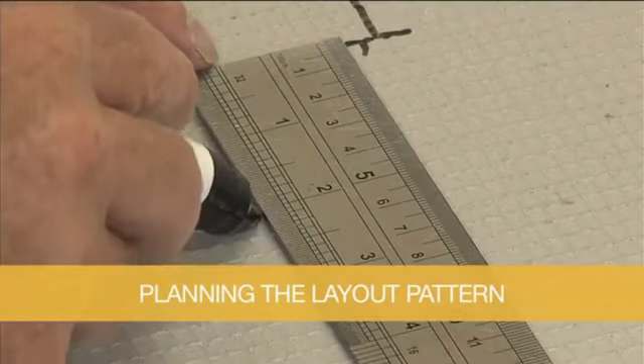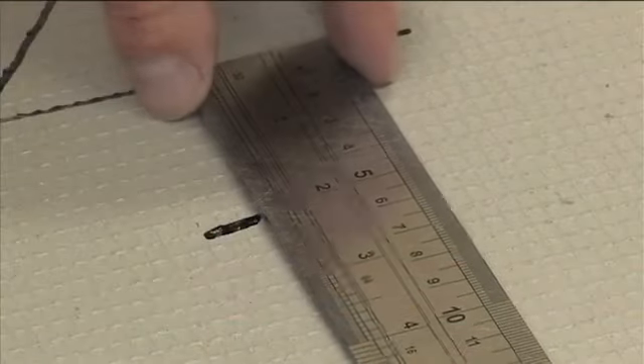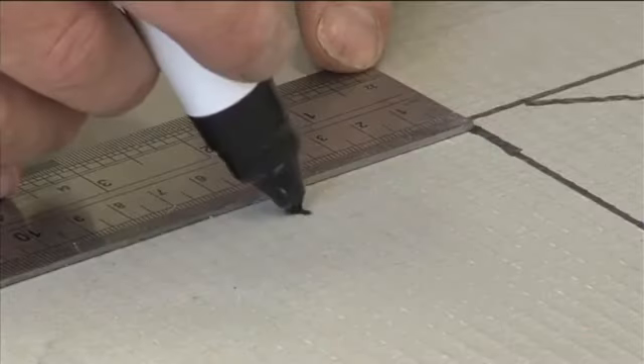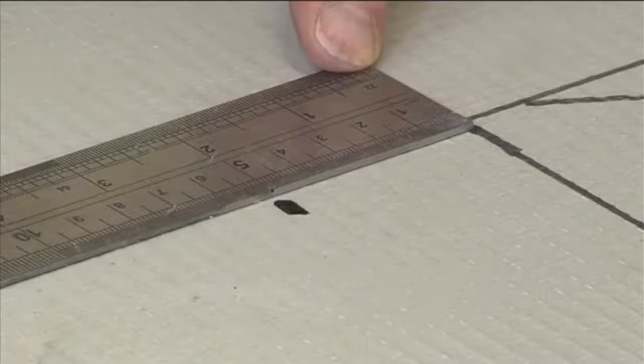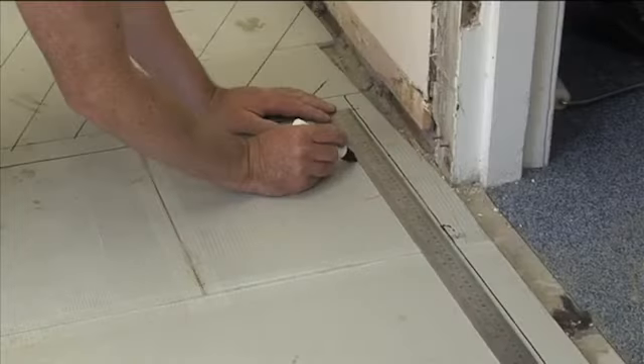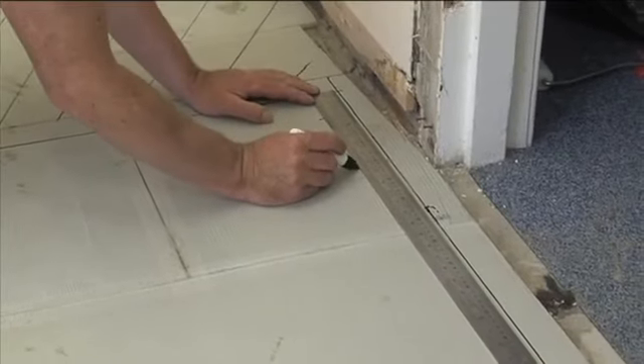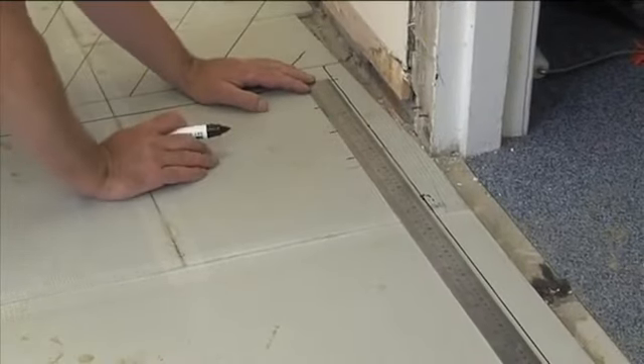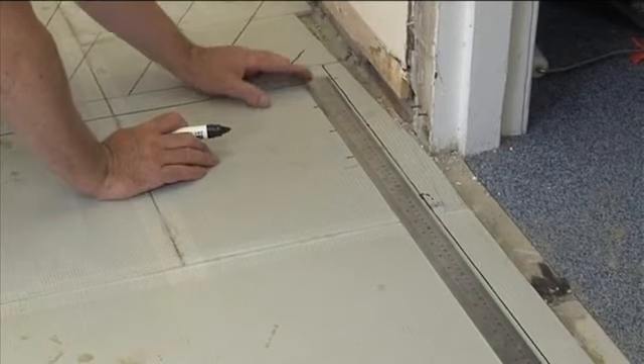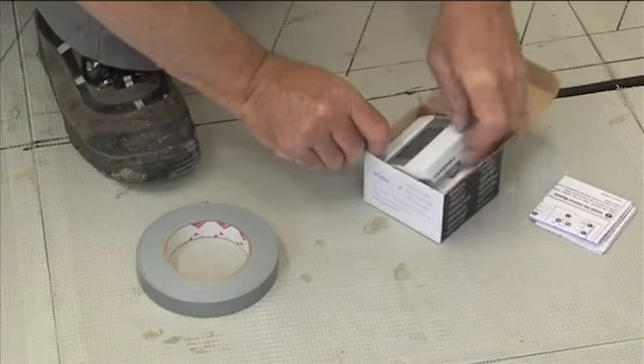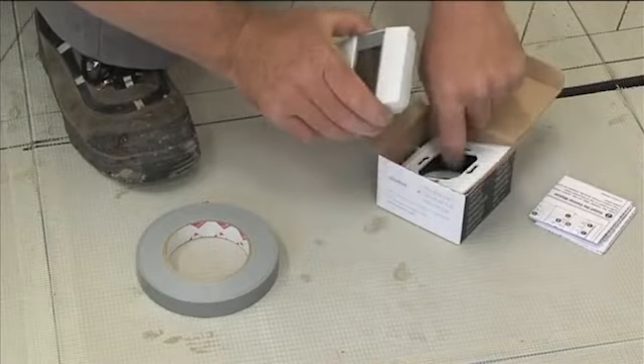Mark the layout of the ECOflex cable on the prepared subfloor with a fibre-tipped pen. Mark the perimeter of the heated area together with the cable spacings obtained from the instruction manual. This will provide your cable laying pattern. Mark your cable start point. Ensure that this is close to the planned thermostat position.